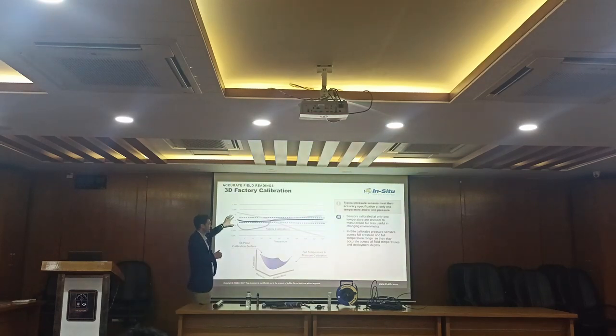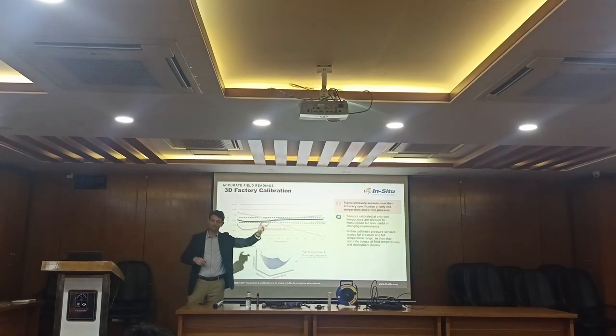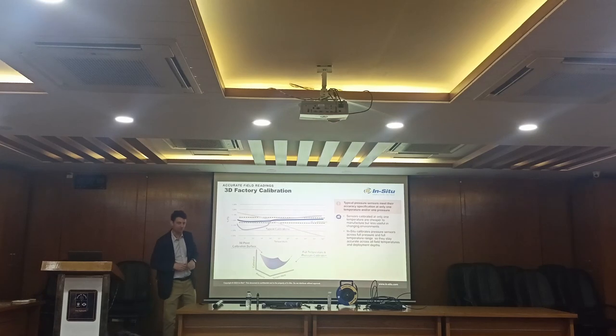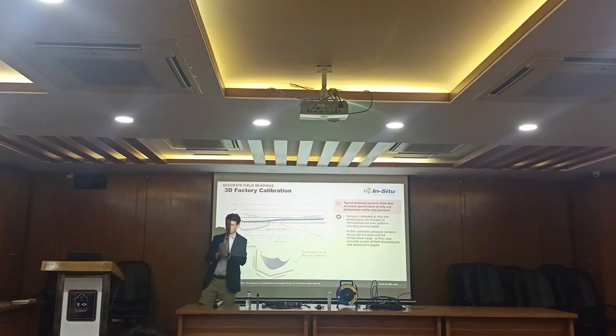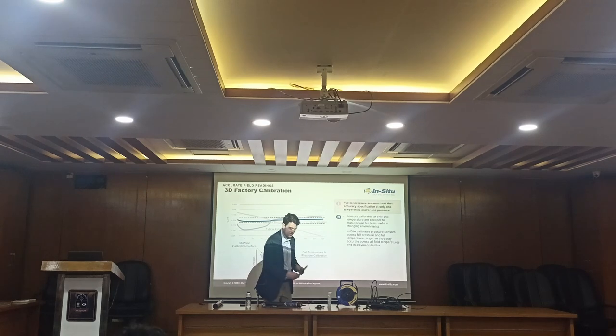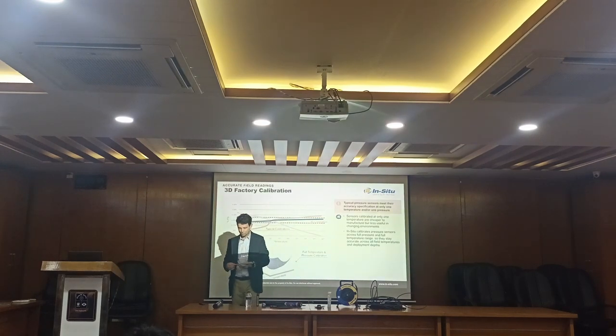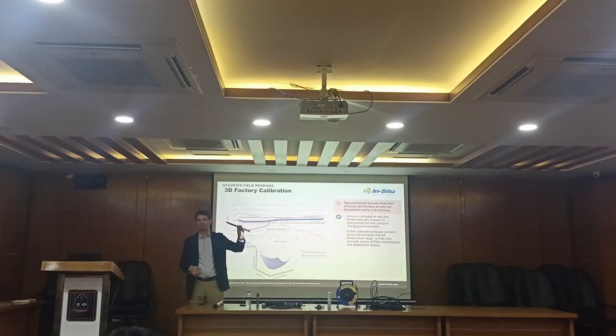So this kind of gets into what I was just talking about with the level sensor, where the accuracy of the sensor can vary over the pressure and temperature range that the sensor is designed to operate. What we're looking at here, to understand that with a pressure sensor very quickly—there's a whole other presentation on this—pressure sensors come in different pressure ranges.